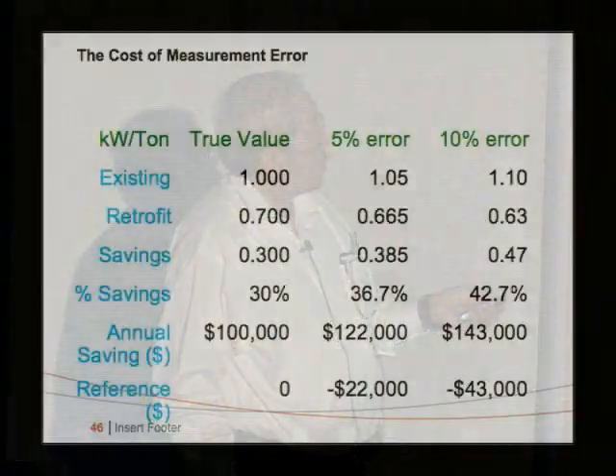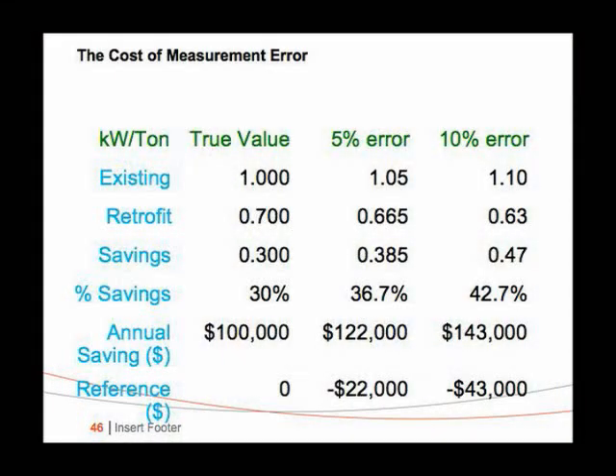So, simple example. Take an existing plant at 1 kilowatt per ton, you retrofit it at 0.7, you save 0.3, it's 30%, let's say that's $100,000 a year. If you follow ARI 550, which is the test standard for rating chillers, 5% error is allowed. And that could lead you to $22,000 error. And in the field, I don't think anybody gets 10% even. You can be $40,000-something out. That's why many shared savings contracts have gone astray, and many owners will not accept shared savings contracts.